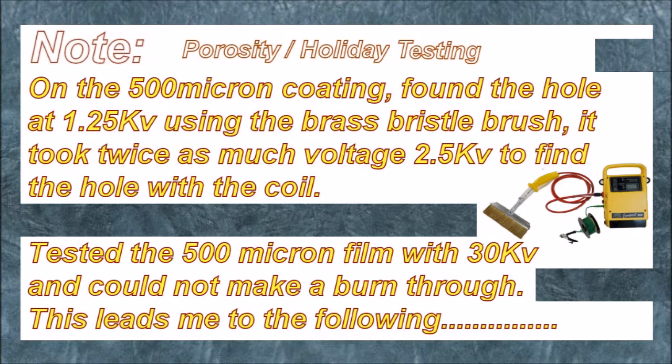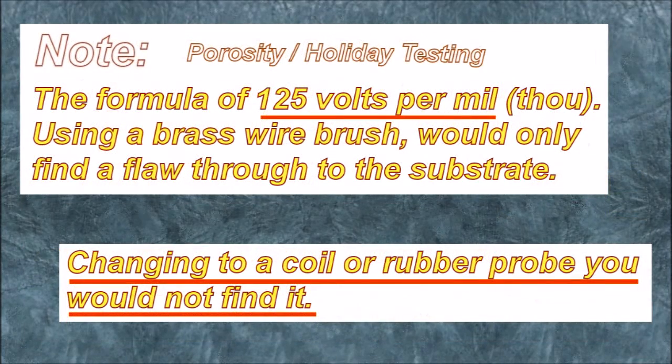Tested the 500 micron film with 30 kV and could not make a burn-through. This leads to the following: the formula of 125 volts per mil (thou) using a brass wire brush would only find the flaw through to the substrate — or should I say, maybe finding a flaw exposing the substrate. Changing to a coil or rubber probe, you would not find it.